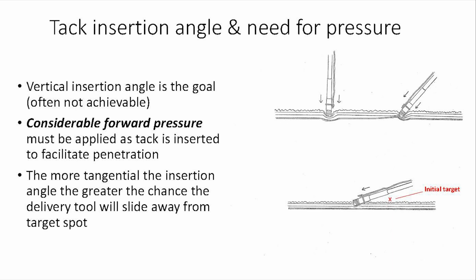The ideal angle between the delivery tool and the bowel wall is 90 degrees since it will lead to vertical insertion. Also, it is necessary to push the delivery device strongly into the bowel wall in order to stabilize the tack position and to maximize the depth of penetration. In the colon, in practice, the insertion angle is often more acute because the bowel lumen does not permit a 90-degree angle. Also, the more tangential the approach, the greater the chances the tack will slide prior to placement.